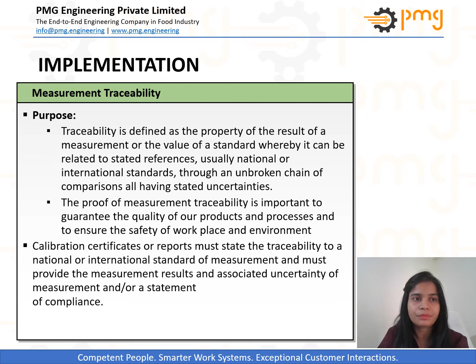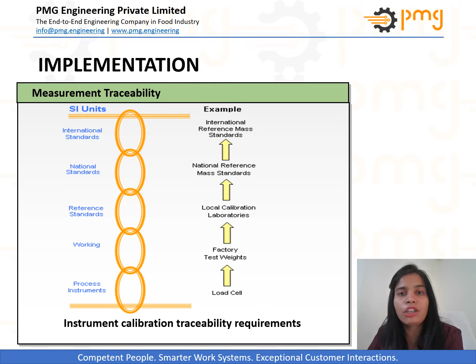As you can see in the present slide, it should be possible to demonstrate an unbroken chain of comparisons, or trace back the accuracy value to a primary standard at SI. In the typical calibration hierarchy for measurement and traceability, each level should be calibrated using a higher standard. When moving up the hierarchy, with each traceable calibration, it is best practice to maintain an accuracy ratio. The accuracy ratio should be 4 times closer to the ideal accuracy of the higher standard.